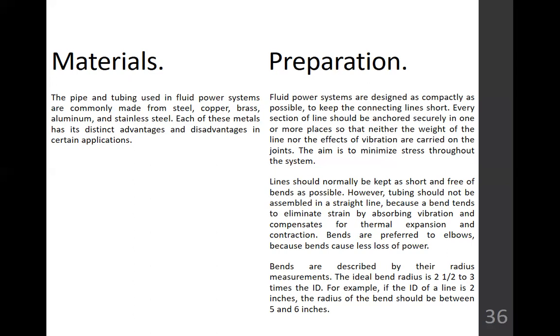Lines should be kept normally as short and free of bends as possible. However, tubing should not be assembled in a straight line because a bend tends to eliminate strain by absorbing vibration and compensating for thermal expansion and contraction. Bends are preferred to elbows because bends cause less loss of power.